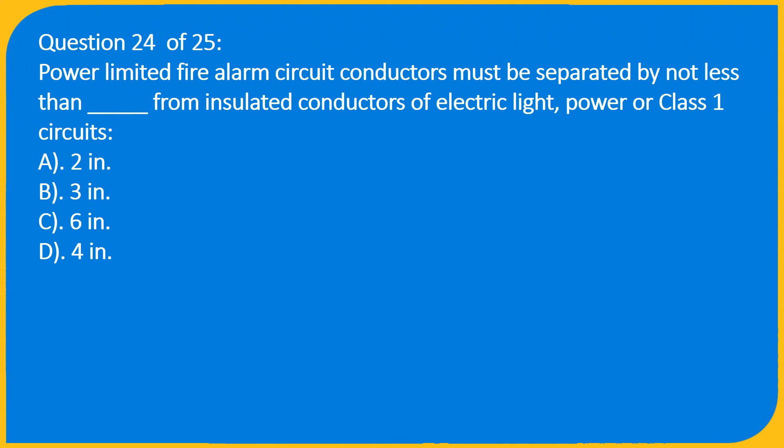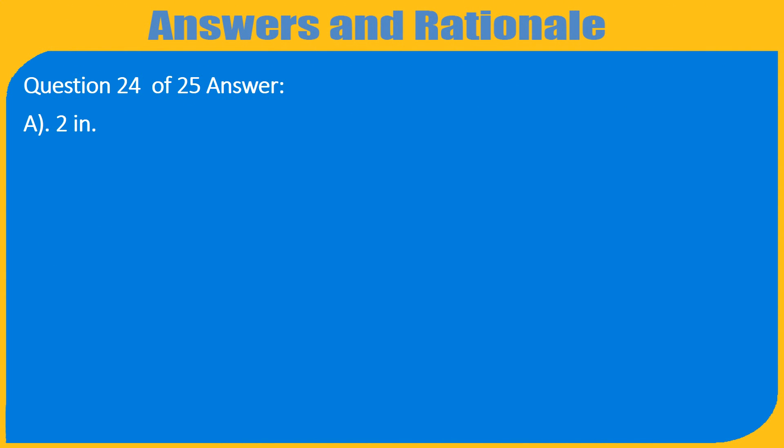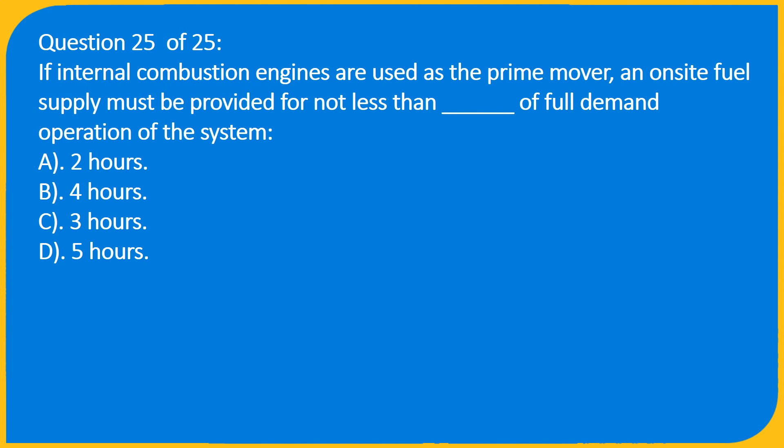Question 24 of 25: Power-limited fire alarm circuit conductors must be separated by not less than how many inches from insulated conductors of electric light, power, or Class 1 circuits? Answer: A. 2 inches.